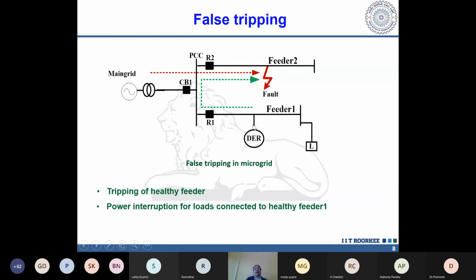So this feeder 1 has one DER connection, but in feeder 2 we have not shown that. For example, for explaining this, we have taken these pictures. This feeder 1 is basically supplying some current to this fault point as well, because the DER will try to push some fault current to this fault point, and the main grid also will try to push some current to that.